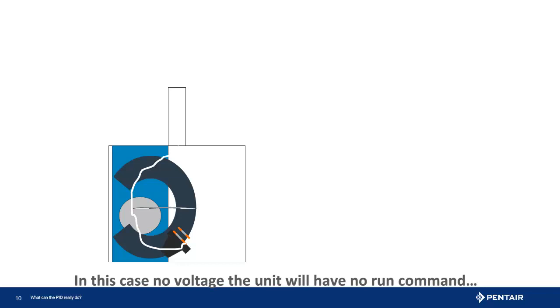Why would I use a run command? Often this is a condition that could correct itself, and rather than setting the input to fault, requiring the system to be reset, a run command will only let the pump work when the input sees the signal voltage. We know the cistern has a fixed amount of water. As it is consumed, the level goes down. If the level gets low enough, the switch opens the points, the input no longer sees the voltage and the drive will stop, but not fault. Once the water level returns in the cistern, the float rises, re-establishing the voltage, and the unit will begin running again automatically.